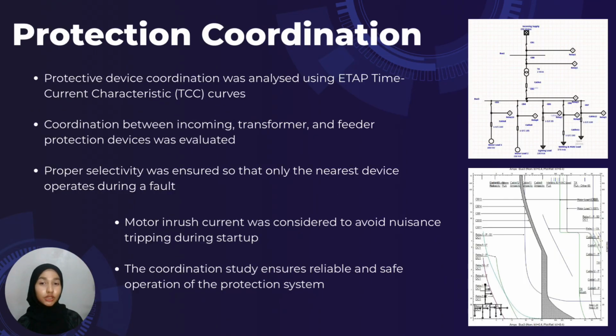Next is protection coordination. For this part, we analyzed the protective device coordination using ETAP time current characteristic, or TCC, curves. The coordination was carried out between the incoming supply protection, transformer protection, and feeder circuit breaker to ensure proper grading of protection devices. From the TCC curves, proper selectivity was achieved, meaning that during a fault condition, only the protection device closest to the fault location will operate, while upstream devices remain in service.